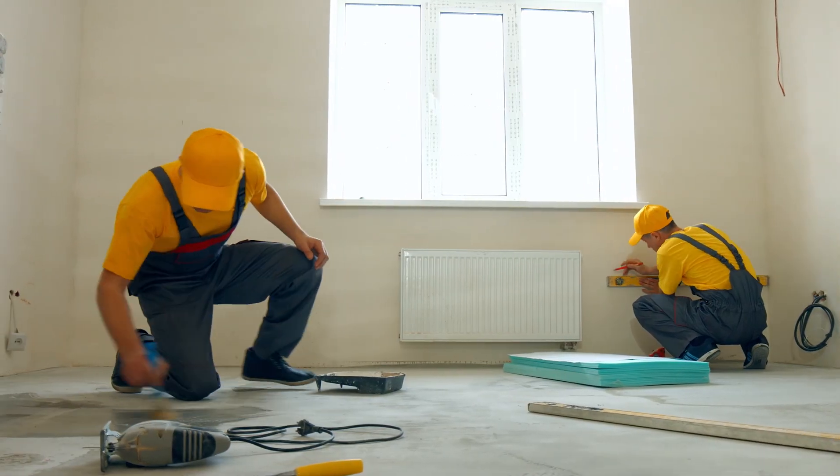Finally, under renovations, I would go for pipework. Make sure you have at least 15mm pipework going to these new radiators. If you have a single panel radiator that's ancient, you need to get rid of that, get a double panel, and have a 15mm pipe going to it. Of course you can run a heat pump on smaller pipework — most commonly maybe 10mm or 8mm — but these are a lot more complicated systems which can cost a lot more money as there's a lot more planning that goes into it. For the cost of a few lumps of copper and the labour time, it is definitely worth upgrading to 15mm.